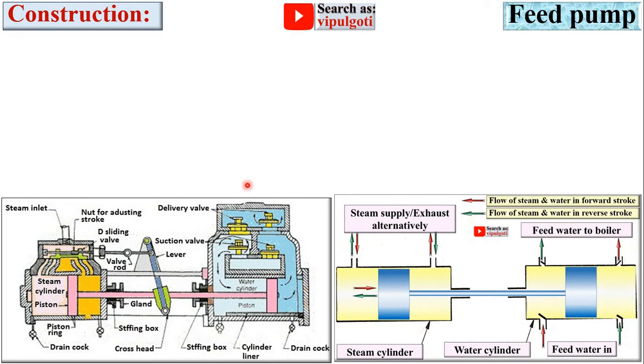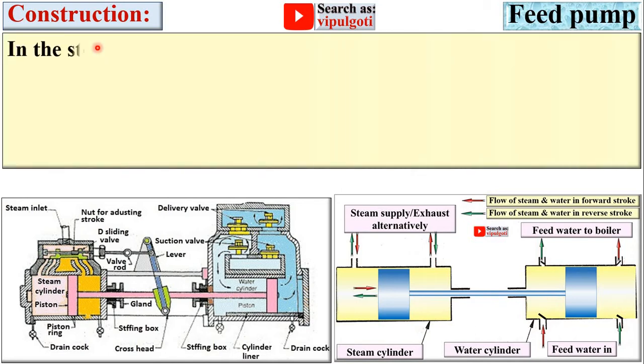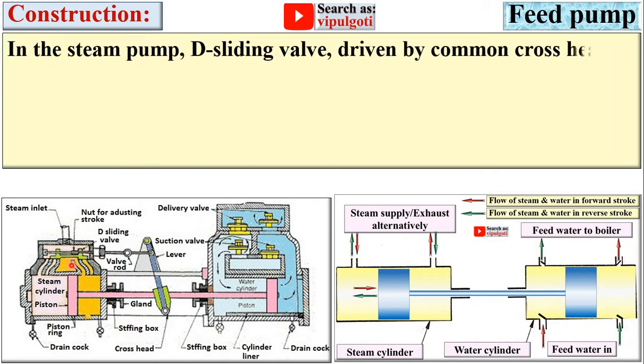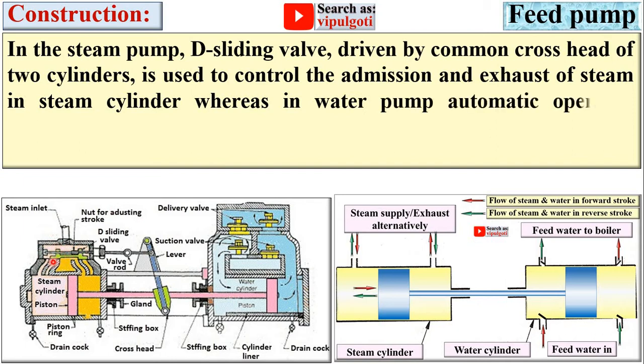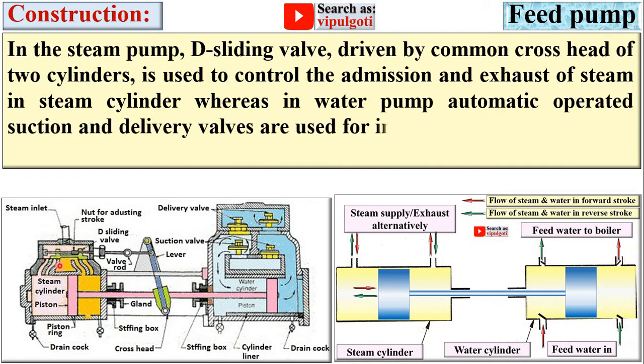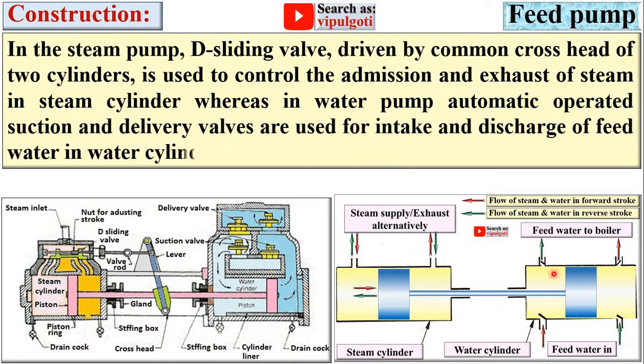This figure is used to understand the construction and can be used for examination purposes. In the steam pump, a D-slide valve driven by the common cross head of the two cylinders is used to control the admission and exhaust of steam in the steam cylinder. In the water pump, automatically operated suction and delivery valves are used for the intake and discharge of feed water in the water cylinder.